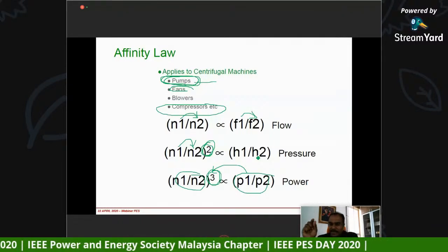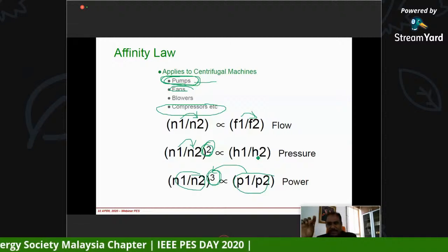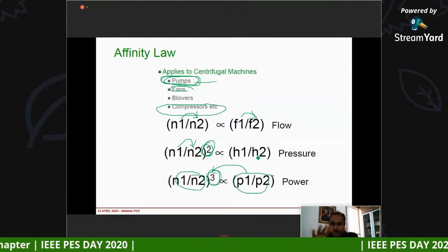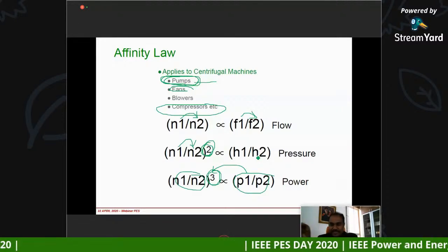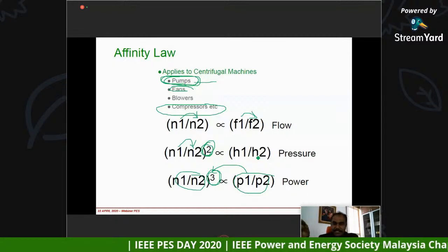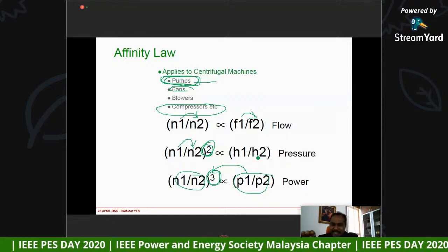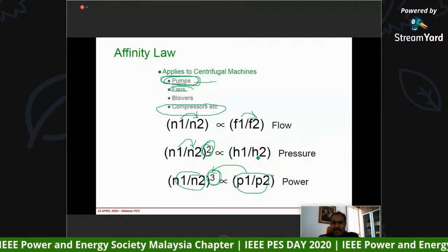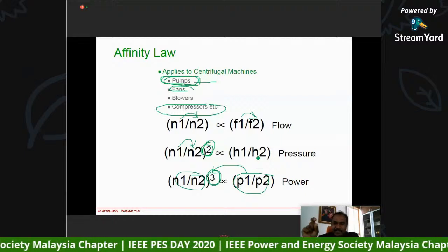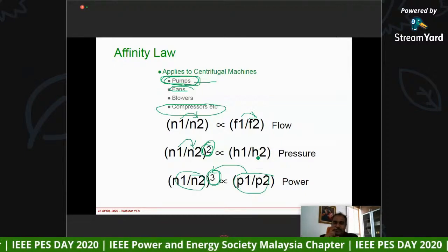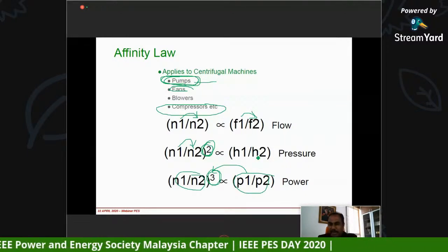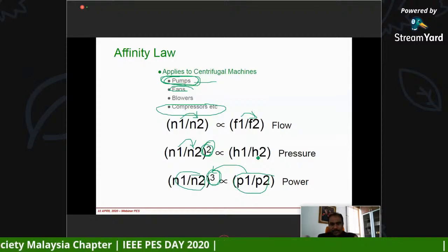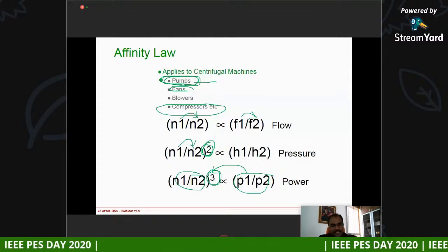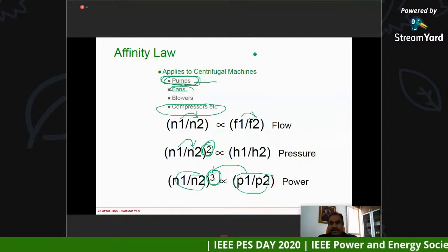When we reduce a little bit of speed, for example, if the motors are always running at 50 hertz all the time, and then we just reduce it to, let's say, 45 or even 46, that means a reduction of 4 hertz, we see a very huge reduction in the power. Because most of the systems are pump and fan systems, which comply with the affinity law, this is always true.